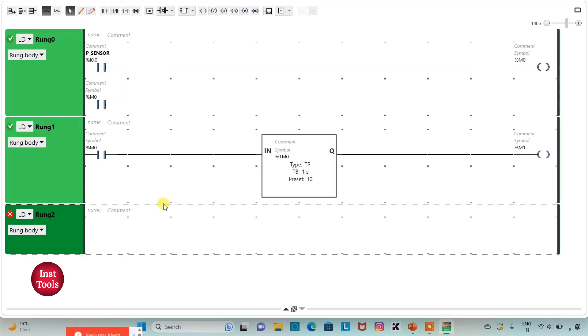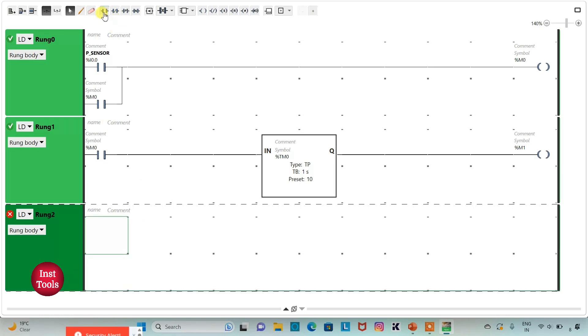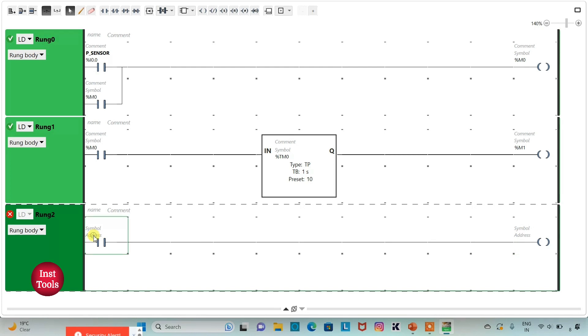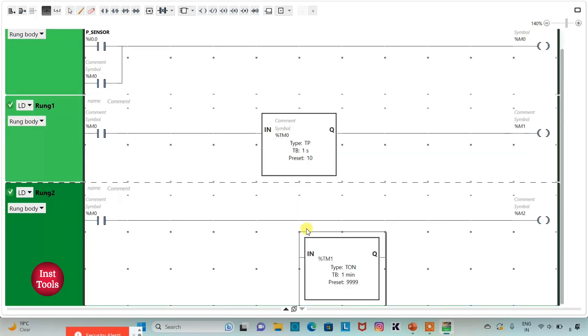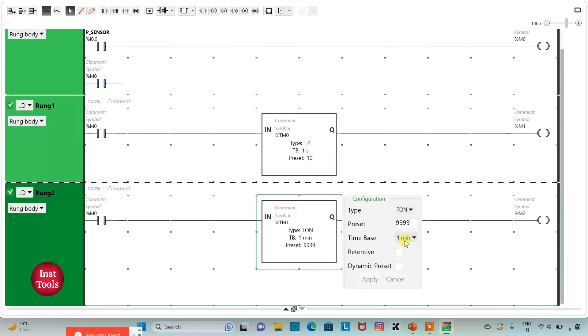I will add a new rung. I will insert a normally open contact and then a coil. I will assign address M0 to the normally open contact and address M2 to the coil. For M2, I will use a timer. I will change it to TON, set the time base to 1 second and preset value to 60 — that is 1 minute — and click Set.